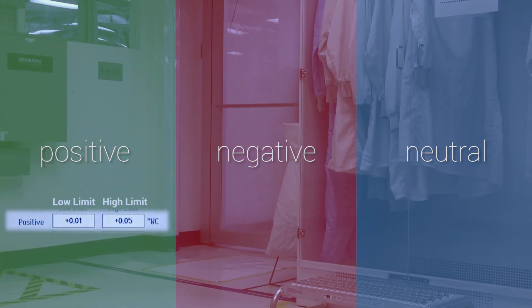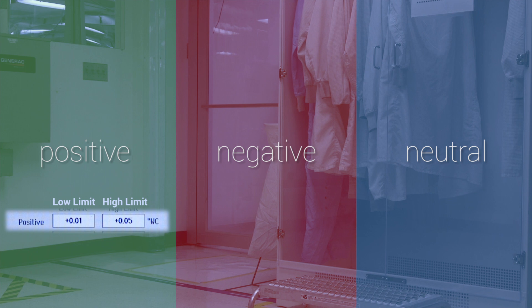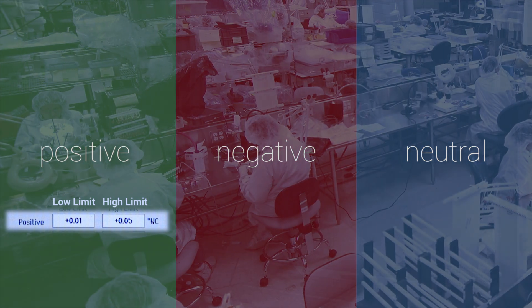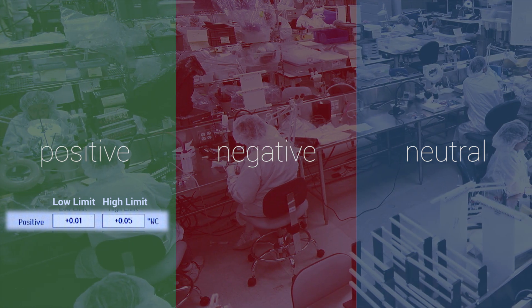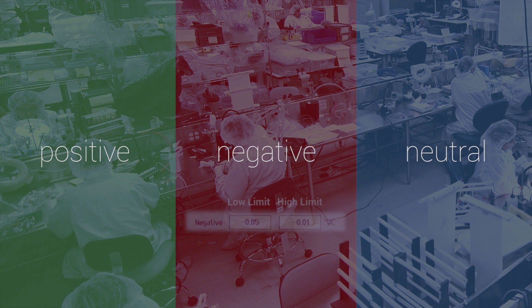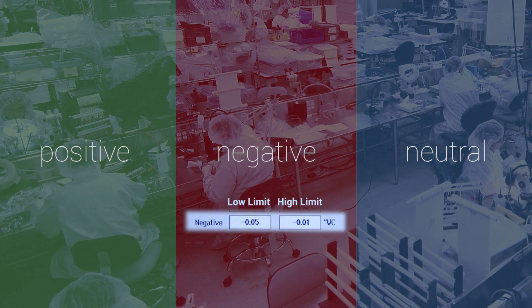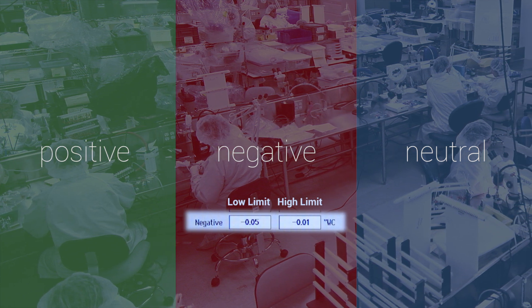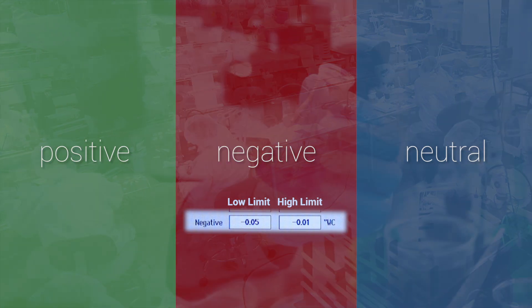A positive room will have an alarm set point slightly above zero differential pressure to some greater positive pressure. A negative pressure room will have alarm set points from less than zero differential pressure to a deeper negative pressure.